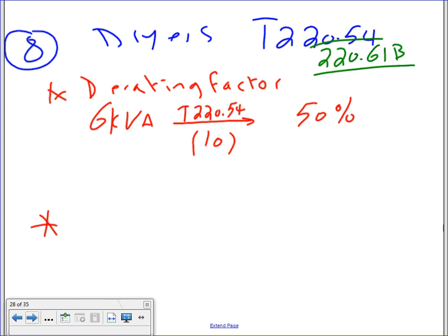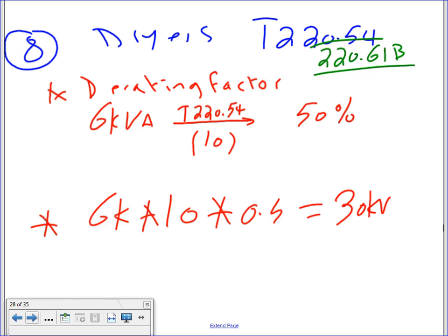Highly unlikely that you and I and everybody in the apartment building will be washing our clothes at the same time, right? So what you do is take your 6 kVA, multiply it by 10, because there's 10 of them, multiply it by 0.5, and ladies and gentlemen, you get yourself 30 kVA. That's the size you're going to carry for the dryers. That's your size for the dryer.